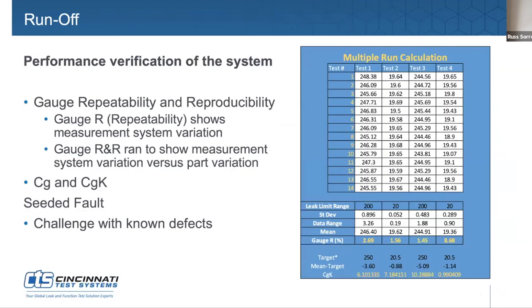Yep. Let's talk about this, it's always a hot topic, and we should probably have a separate session just talking about runoffs. But let's help people wrap their mind around it, because I know from my experience when I was at Cummins, when we had a gauge R&R for the manual gauges that we would use, our expectation was it'd be 10% or less. And then when I got into the leak test industry, because of all the dynamics that go into it, it's between 30 and 20, or at least less than 30, and then less than 20, obviously depending on the application. So let's talk through where that has come from since the mid 90s when we were first exposed to it.